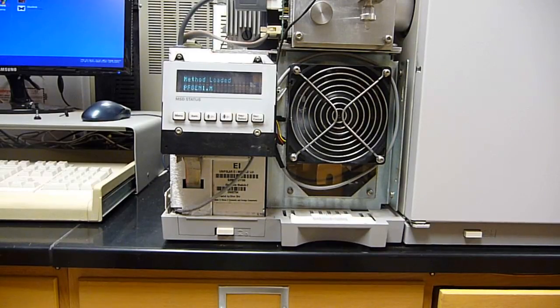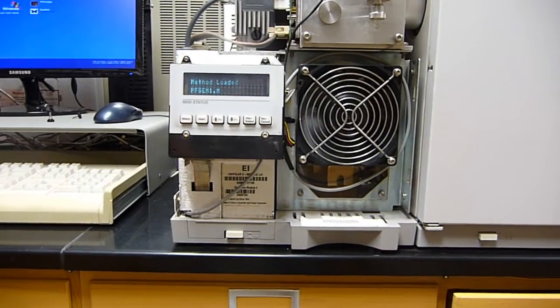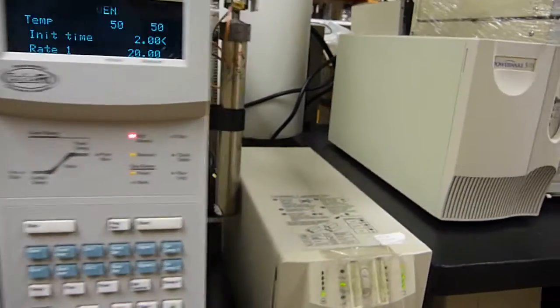So what we wanted to do was, if we had any sort of power outages from ice storm or electrical generation problems, we want to be able to have the rough pump keep working and the diffusion pump, even if it doesn't have power to it, still have the cooling functioning. So one way to do that is UPSs.